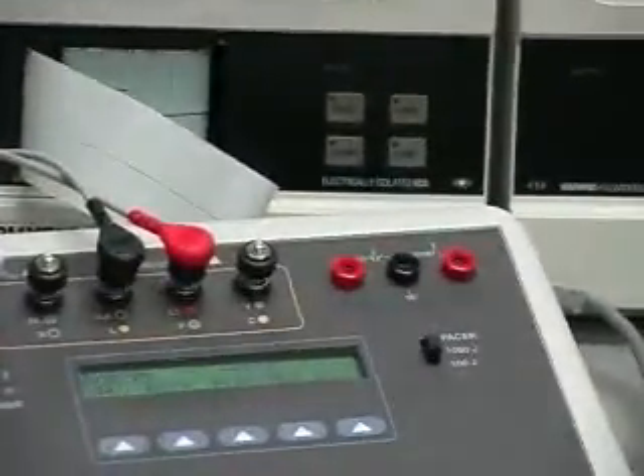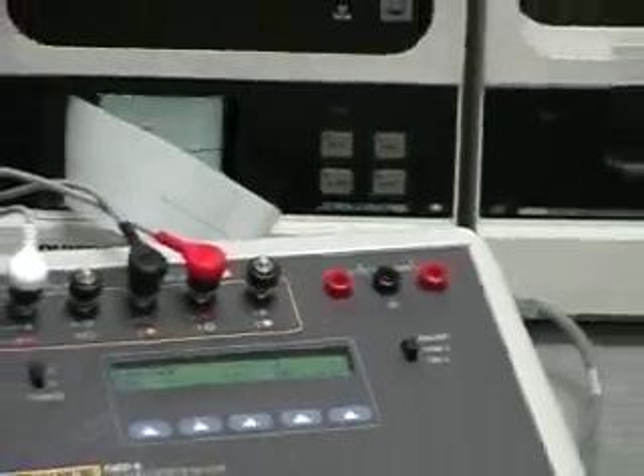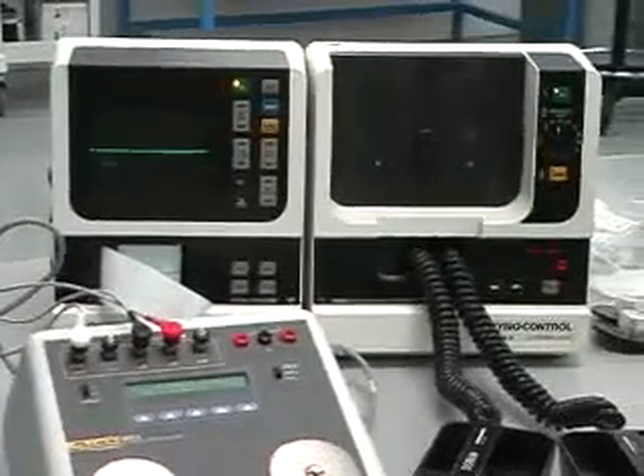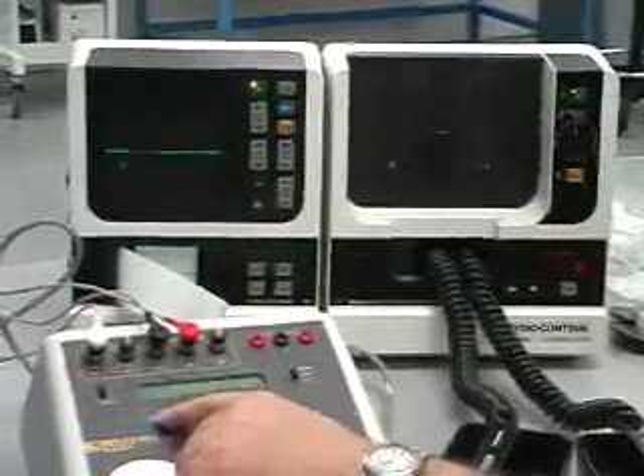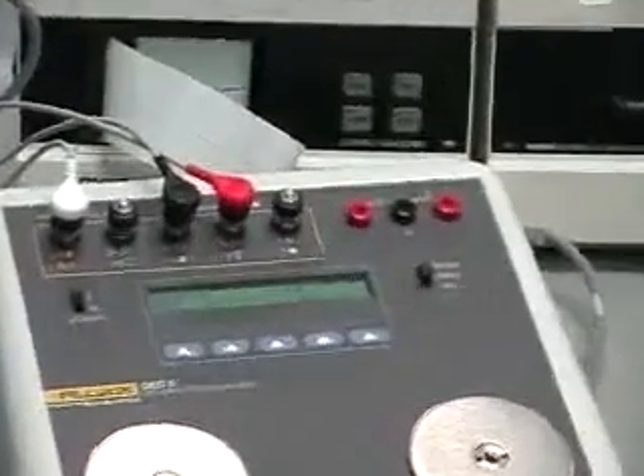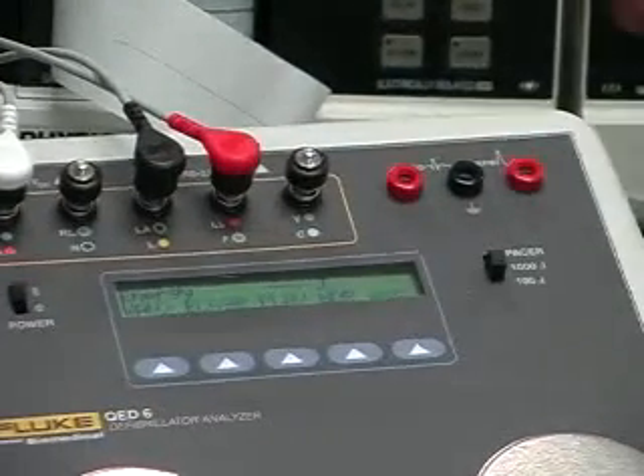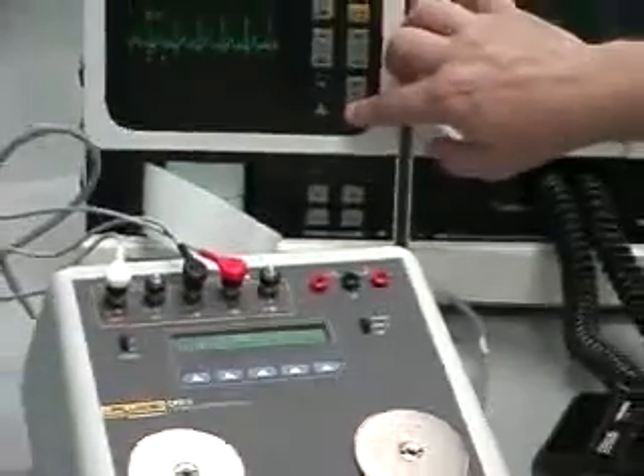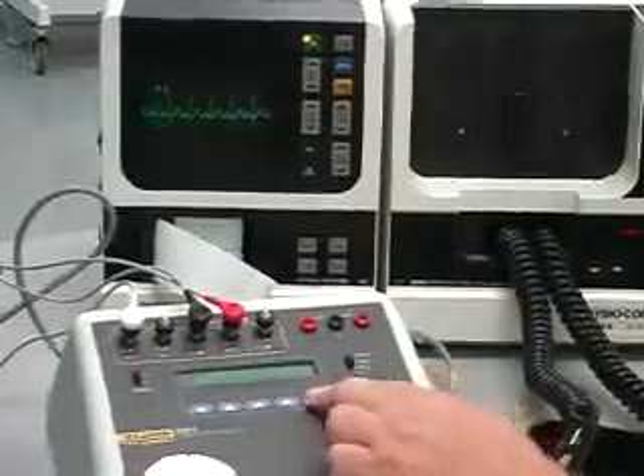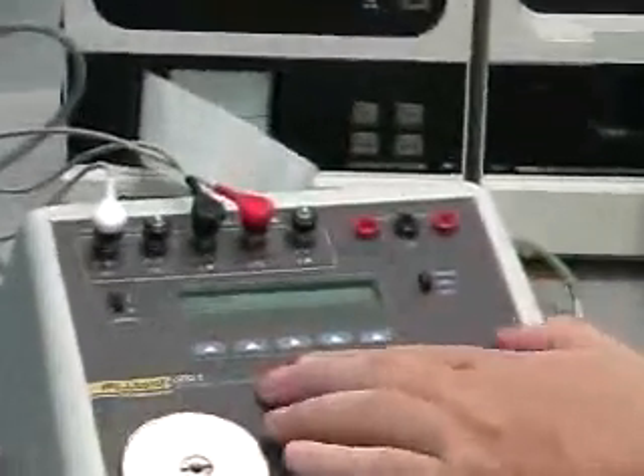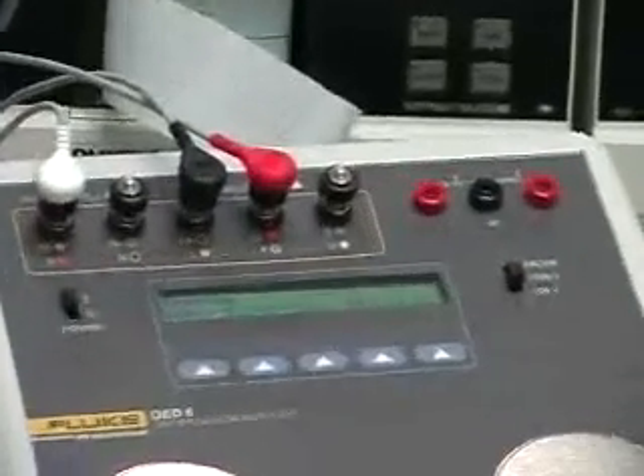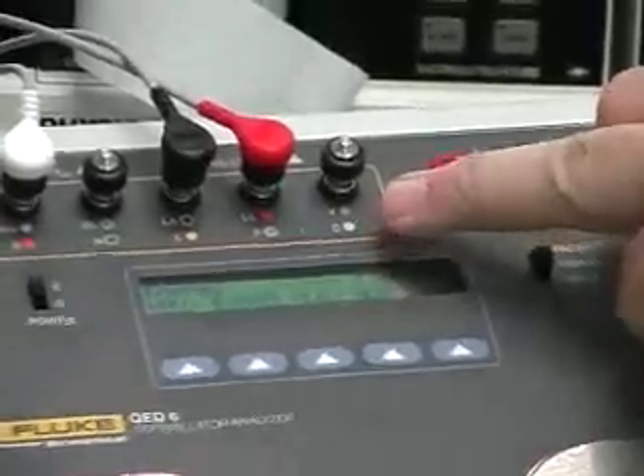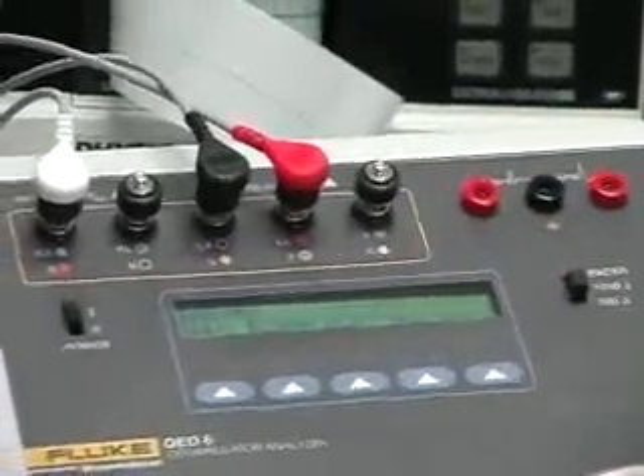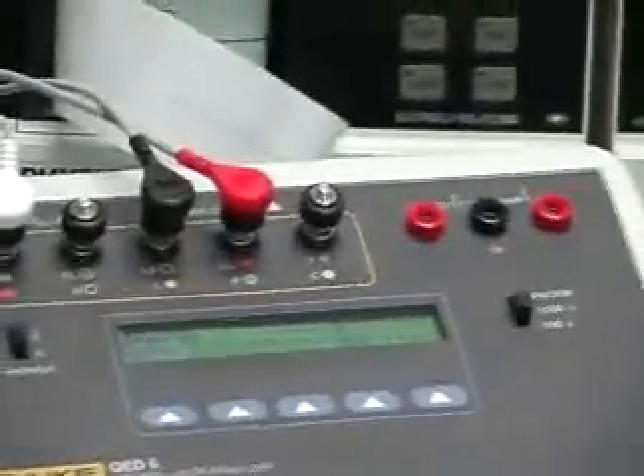Obviously, if you sense an asystole or a zero, that's nothing for the automatic defibrillator to deal with. It's not designed to be interactive with that selection. And we just circle back again to the initial selection of the 90 beat per minute ECG. I'll just leave that one on for right now, and turn the volume down a little bit. Okay, right now we are in the energy menu, and you can tell that by what's on the top screen. It shows there is a spot that will display energy as soon as we charge and then discharge the defib into the analyzer.